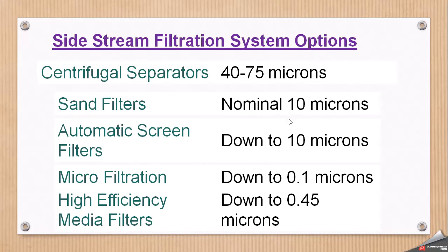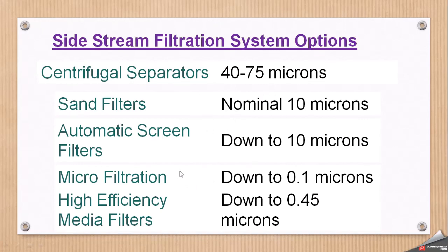There are several types of side stream filtration options, differing by filtration size. Centrifugal separators handle particles of 40 to 75 microns. Sand filters have a nominal rating of 10 microns. Automatic screen filters filter down to 10 microns. Micro filtration operates at around 0.1 microns. High efficiency media filters work down to 0.45 microns. Detailed discussion of each type will be covered in future videos.